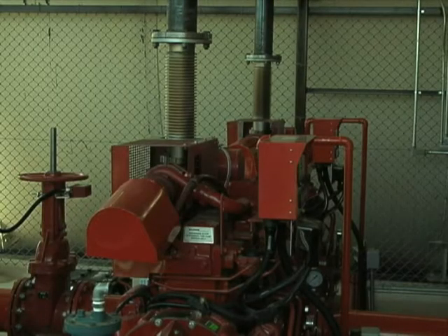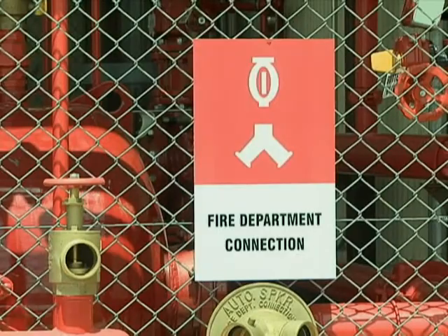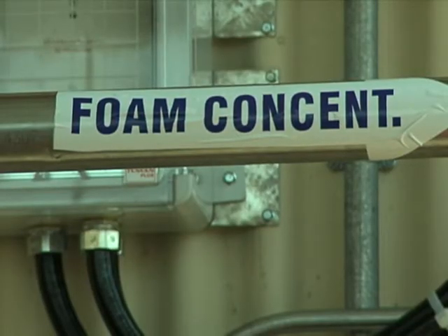With the test today, if there were a fire in our hangar, it's going to take roughly about 30 seconds to fill it with foam and basically snuff out the fire. The $250,000 system protects over $12 million of aircraft and equipment.